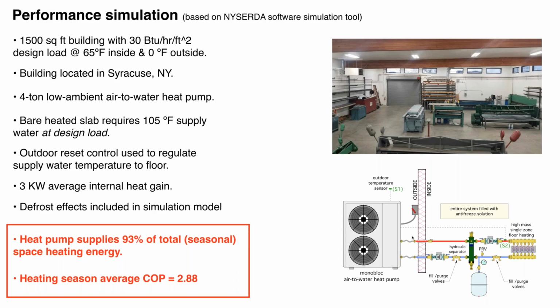I just took a 1,500 square foot building with a fairly high design load, 30 BTUs per hour per square foot. Assume we're trying to maintain 65 degrees inside and the outdoor design temperature was 0. We put a 4-ton low ambient air-to-water heat pump into the heat source model. The bare slab was assumed to require 105 degree water temperature at design load. We did employ outdoor reset control under partial load conditions. We assumed that we had a 3 kilowatt average internal heat gain from equipment, lights, and people. And we definitely included the derating effects of defrost.